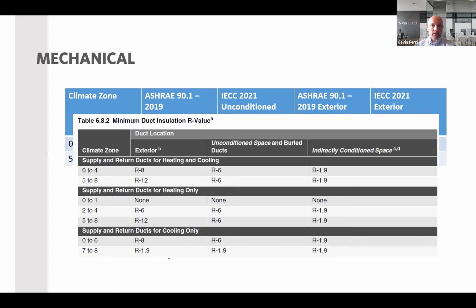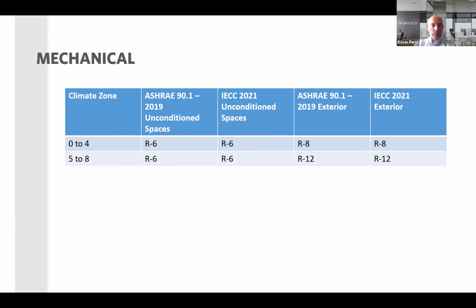And what I mean by that is, here's the table. So this is cut out of ASHRAE. And so you can see that supply and return ducts for heating and cooling is a category. Supply and return ducts for heating only. Supply and return ducts for cooling only. So ASHRAE has more options that you would have to follow to show, based on your system's capabilities, if it's heating only, cooling only, or does both. So the table that was on before does both. Most of the systems we deal with do both, so that's why I showed that it's very similar no matter which pathway.